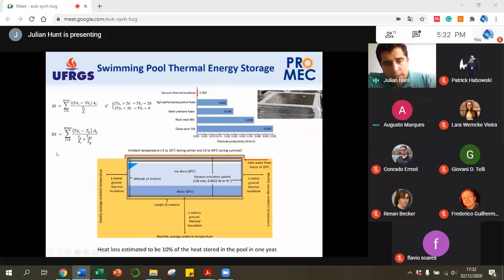But then I calculated the heat loss, and it turns out that with 120 millimeters, so about 12 centimeters of thermal insulation with vacuum thermal insulation, you can result in 10% energy heat loss in the whole year. So you fill up a pool full of this ice, and with this amount of insulation, this layer reduces the heat loss potential, because the temperature here is 20 degrees when the system is actually working, when you're actually cooling the house.